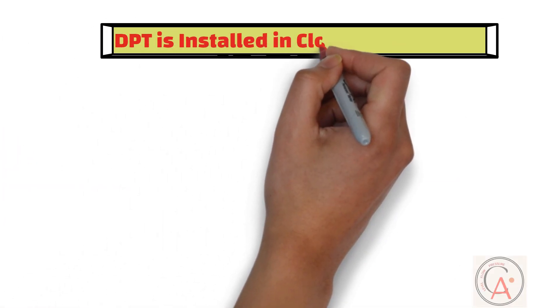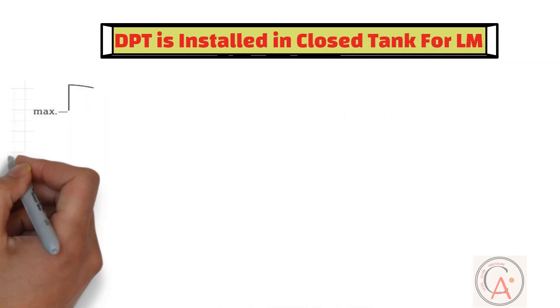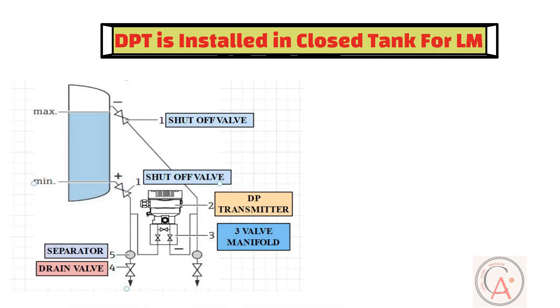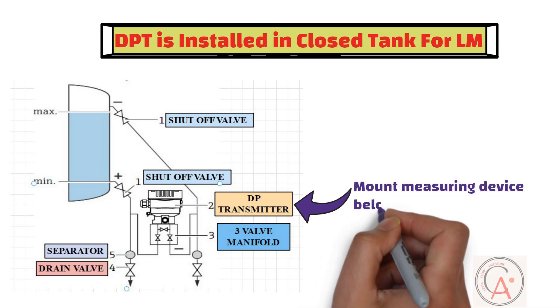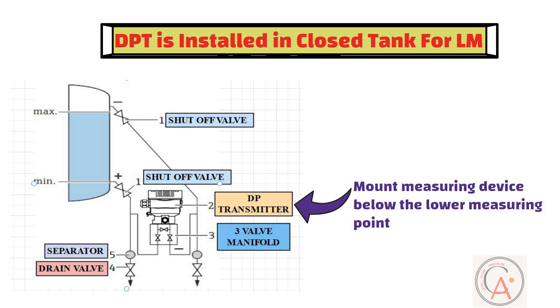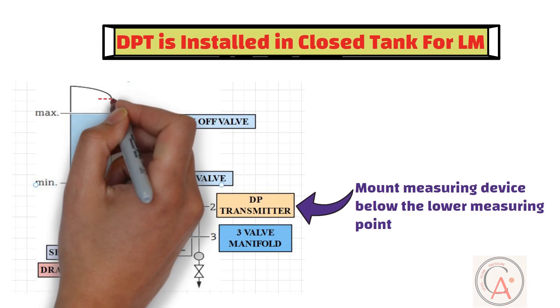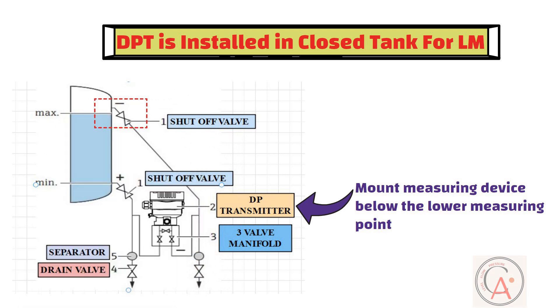Let's take the second scenario, when a DP transmitter is installed to measure level in a closed tank. As you can see, mount the measuring device below the lower measuring connection so that the impulse lines are always filled with liquid. The low pressure side needs to be connected above the maximum level. Additionally, the separator and drain valves are useful for capturing and removing sediment when liquid level measurement is done in media with solid parts such as dirty liquids.